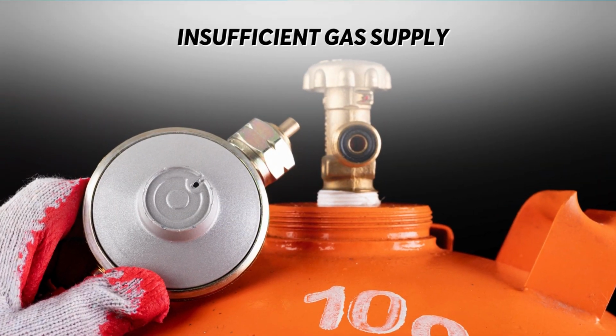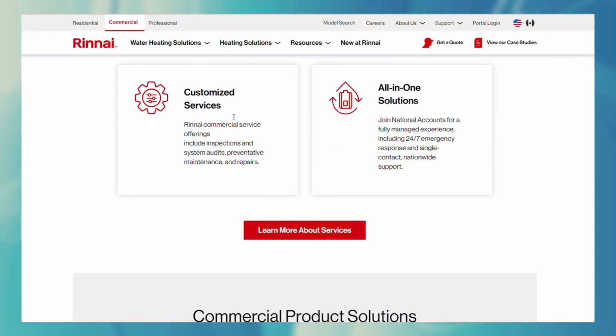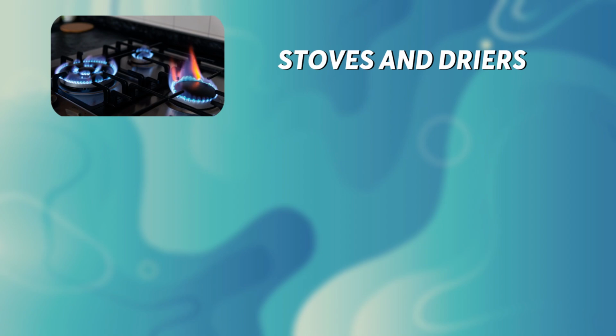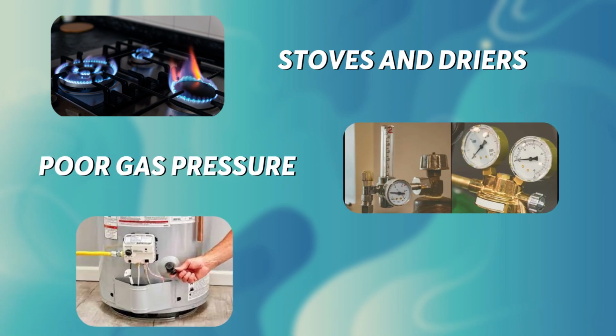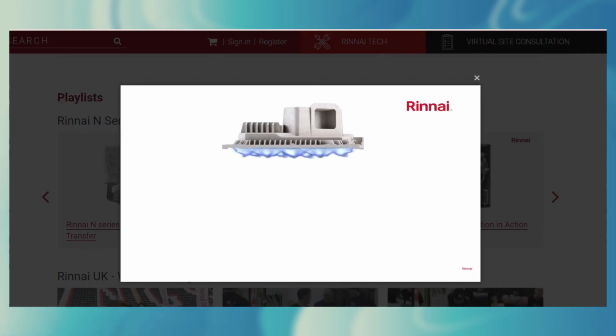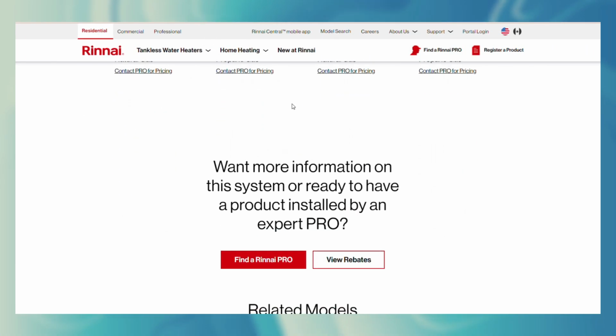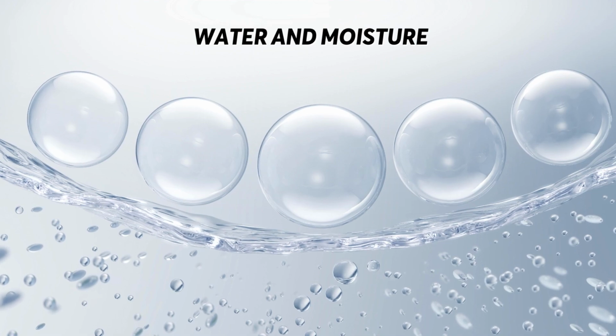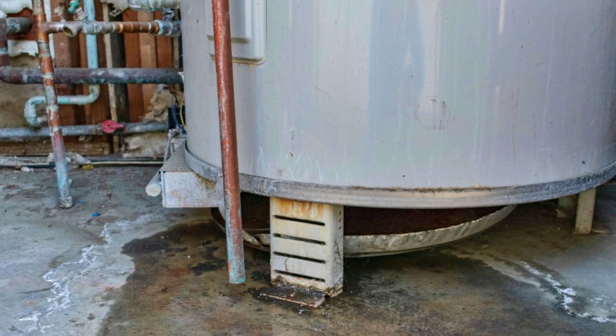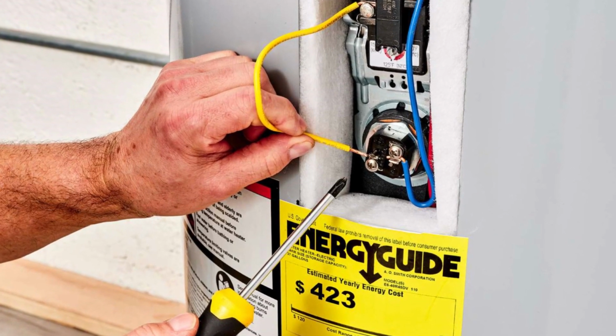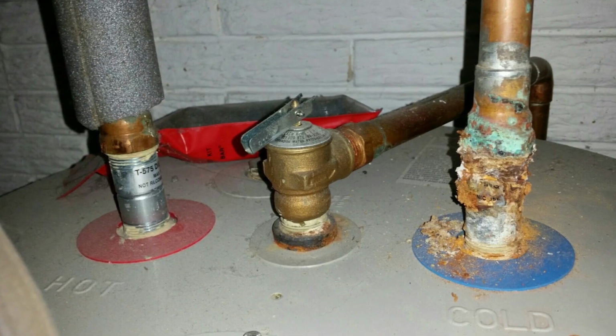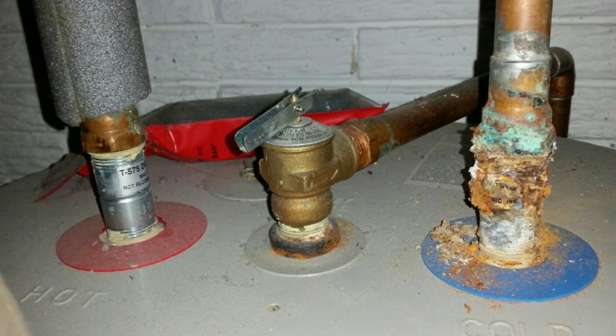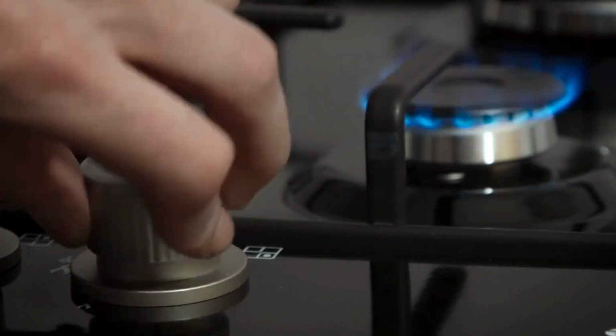Insufficient gas supply. To function, your Rinnai water heater needs a sufficient gas supply. Other house appliances like stoves and dryers, poor gas pressure and airlocks in gas chambers can deplete the gas available for the water heater. It will therefore be unable to ignite. Water and moisture. If water accumulates in the unit's system, it can negatively affect circuits and connections. Moisture can also cause erosion in pipes and other components, which can make ignitions fail.